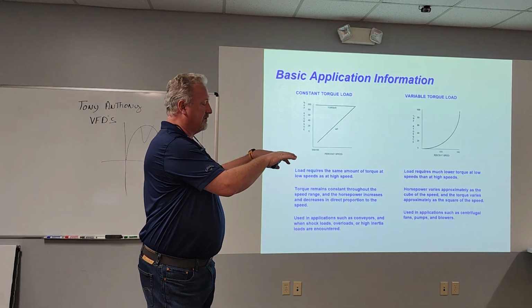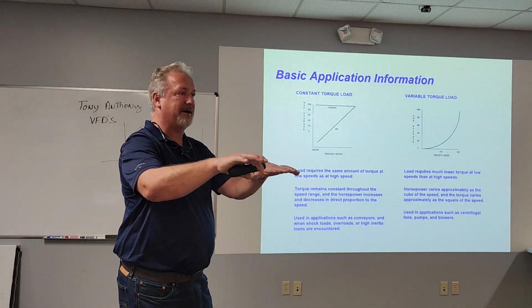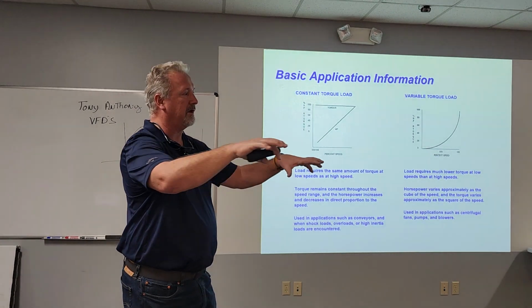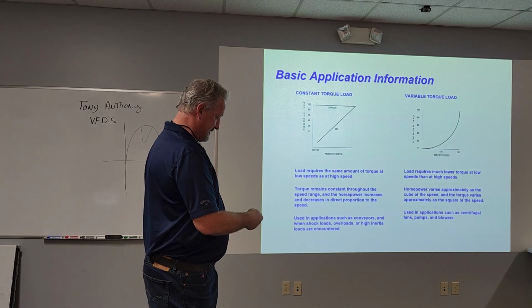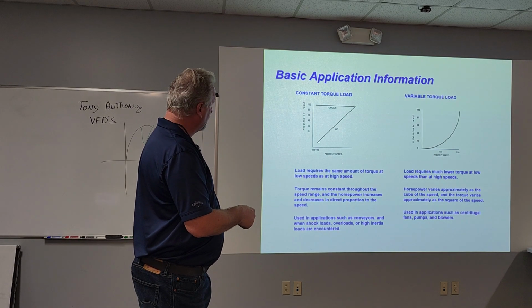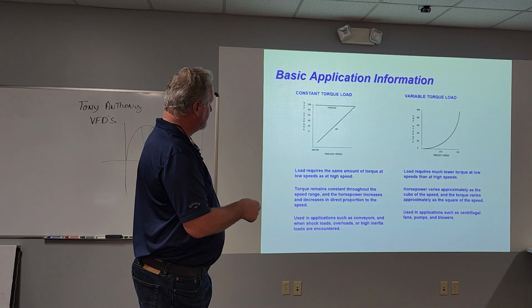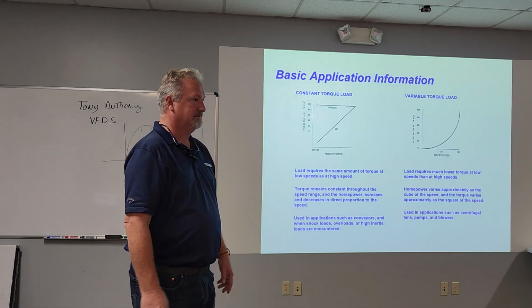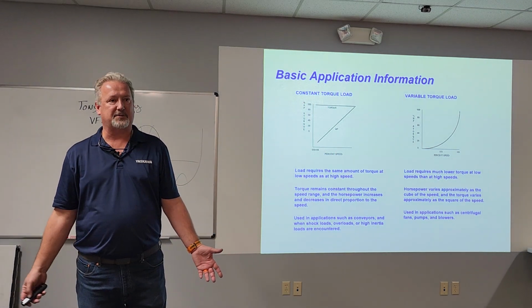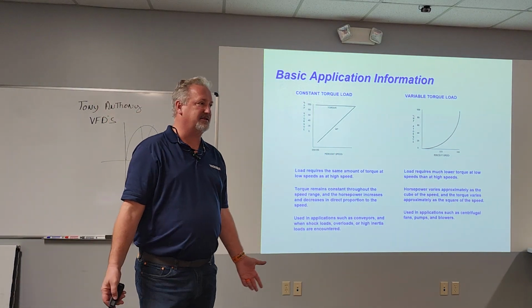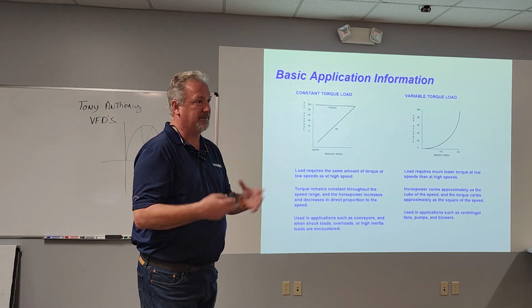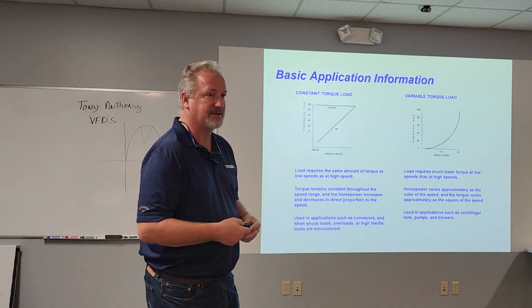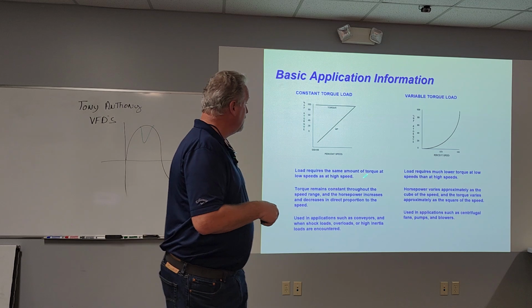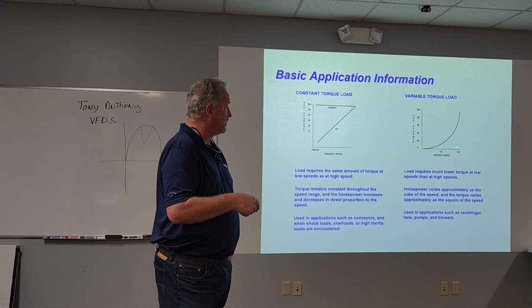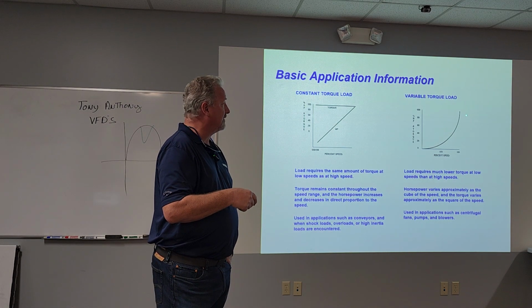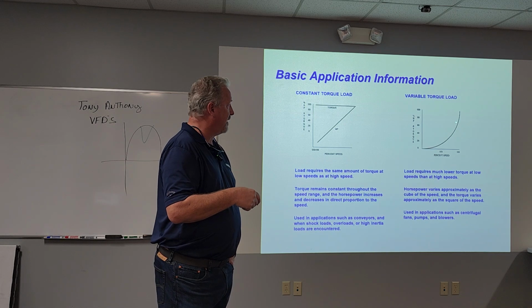On a conveyor, the torque required to move that load doesn't depend on how fast it's going. It's based off the weight of the load on it. This is the speed on the bottom line here. So whether we're running at a real low speed or at full speed, the torque is pretty constant across that, no matter how fast we're spinning that motor. That's called a constant torque load. It actually takes a little bit heavier duty drive than we use in the HVAC world normally. What you have almost always are variable torque loads, centrifugal pumps and fans.